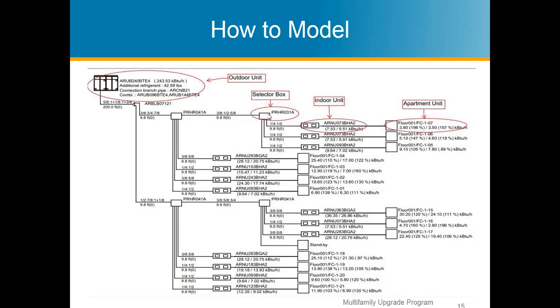So you have an outdoor unit, then you have your selector boxes, and then you have your indoor units. And selector boxes are going to be matched up with different residential apartments. And I'm going to get into zoning here in a second, because it's very important to make sure that when you're using a heat pump or heat recovery VRF system, the zoning is set up in a manner that you're going to reap the benefit of sharing that load.